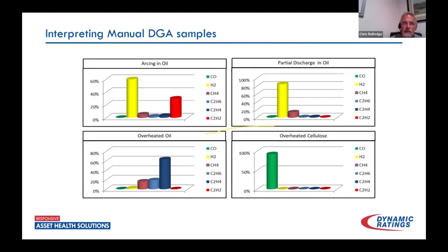One other thing I think is important to understand when looking at partial discharge, at least in my experience, is that it tends to change over time. So, we can have stray gassing in oil. We can have something due to loading, something due to harmonics, some that are producing that 150C that would give us that hydrogen value. True partial discharge tends to grow over time.